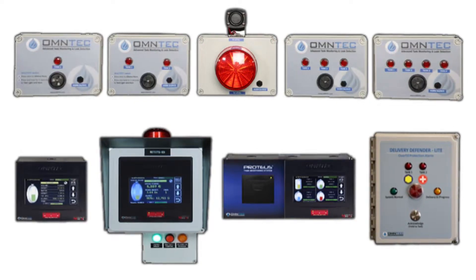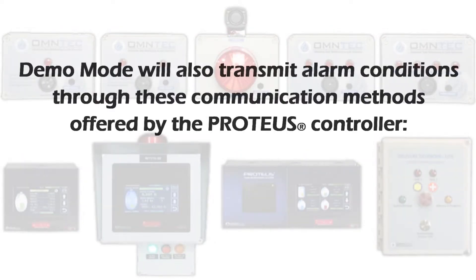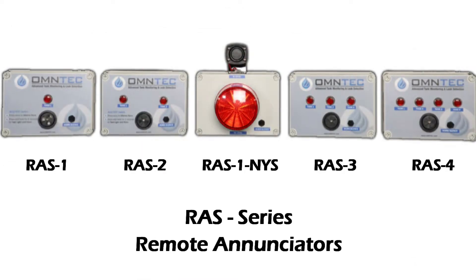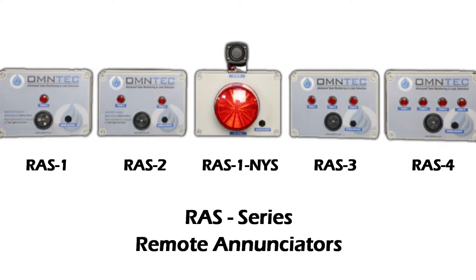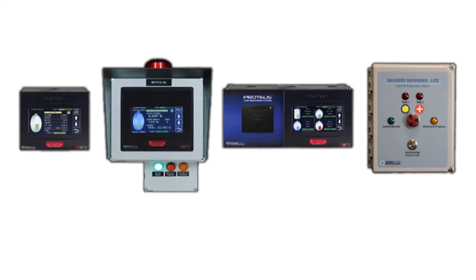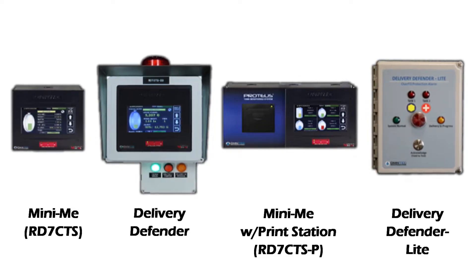Demo mode is used for testing the operation of alarms in regards to remote annunciators and displays. Demo mode will also transmit alarm conditions through the communication methods offered by the Proteus controller: RS-232, RS-485, ModBus, BACnet, and 4 to 20 milliamp converters. Testing RAS series remote annunciators requires that MCU and/or XBR B8 events have already been programmed and the units are wired correctly. Remote displays such as the Mini Me and Delivery Defender require that the correct communication mode has been established.